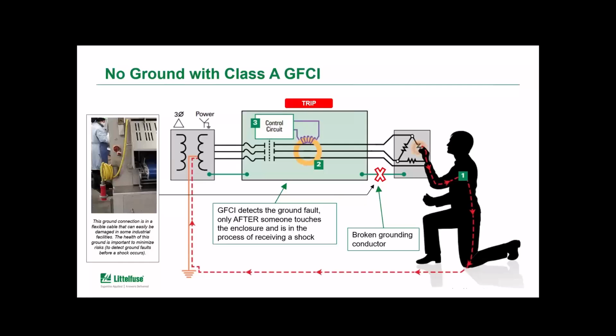Now, when we think about industrial equipment, I just want to highlight one thing here. You can see that photo with the piece of equipment used in food and beverage. The yellow flexible cable is coiled up there. That cable is the link between the equipment and the power system. And with cable laying around, it's easy to think how cables can be cut, run over, pinched, stretched, which can cause damage to the grounding conductor. So that's really one of the reasons why people receive those shocks on the 480 or 600 volt equipment. When a ground fault occurs, the breaker may not be able to sense the current because of damage to that grounding conductor.